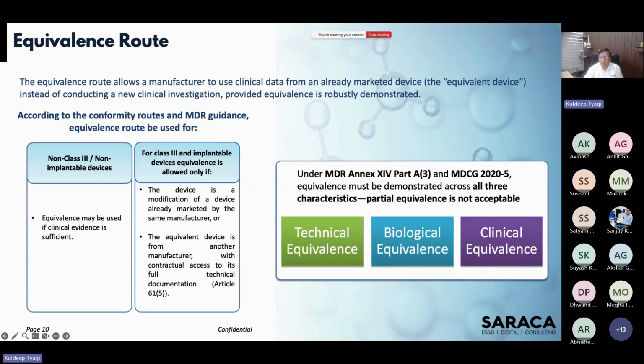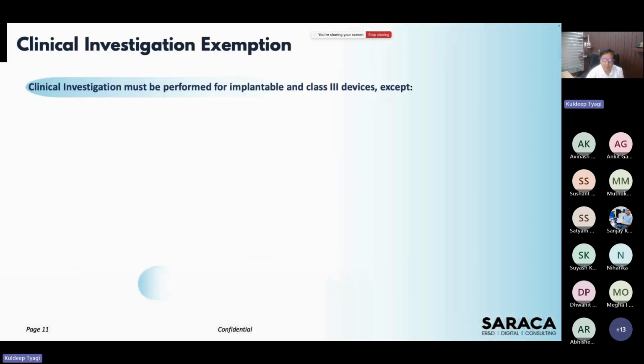But if you want to claim equivalence, you need to demonstrate three things: technical equivalence, biological equivalence, and clinical equivalence, right? If you have only two of them or one of them, it's not going to work. So you have to do an exhaustive, thorough study to make sure that you have all three agreed or approved to make sure that this is equivalence. If you do not, then partial equivalence will not provide you any kind of relief when you submit your CER or tech file for a notified body's review. Okay, let's jump on to the next one.